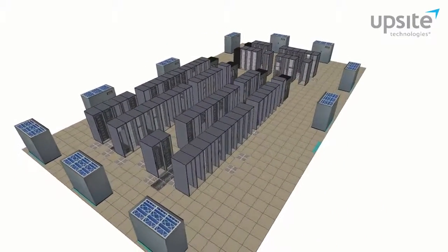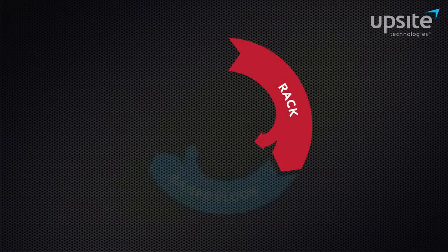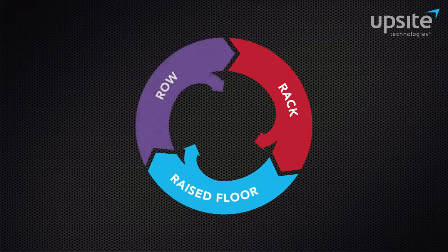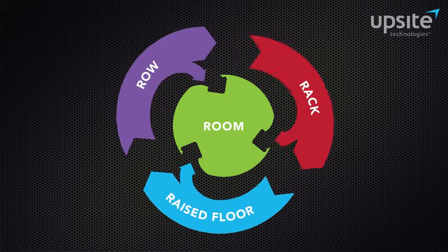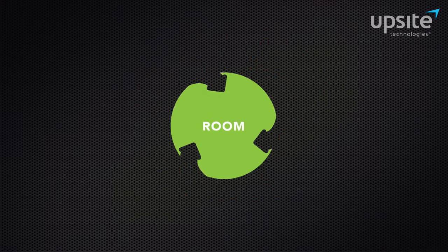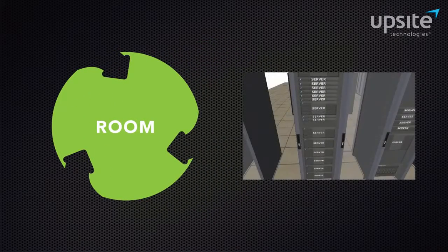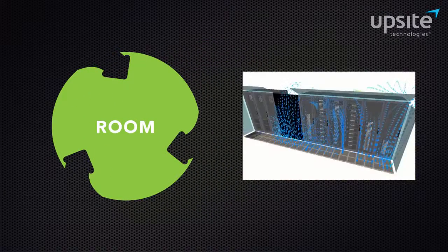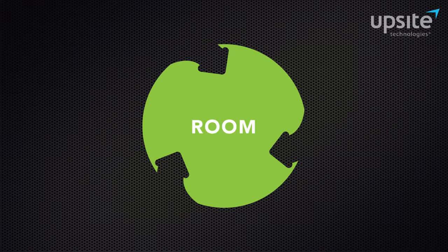The 4 R's of airflow management addresses the data center at each of these 4 levels: the rack, the raised floor, the row, and the room. Cooling optimization is an iterative and ongoing process. The 4 R's methodology reflects this, with the room serving as the central check-in point. After making changes in the rack, raised floor, or row elements of the room, it's important to make adjustments at the room level or the cooling controls to realize benefits.